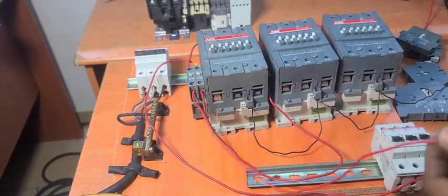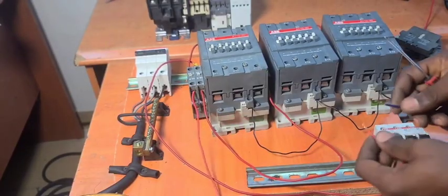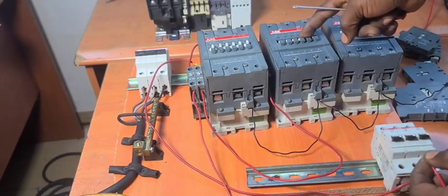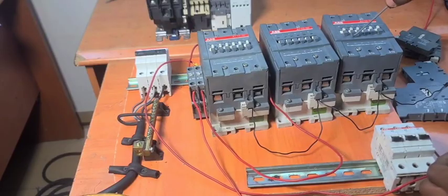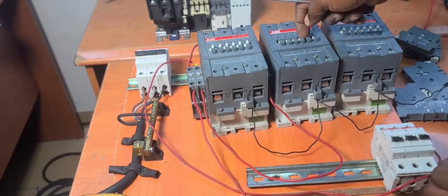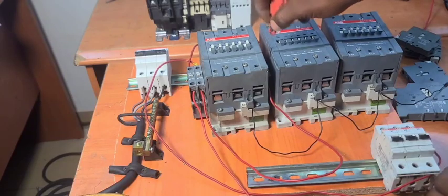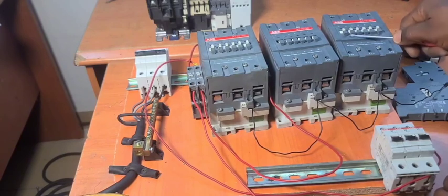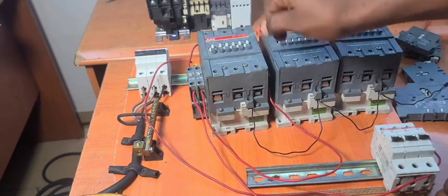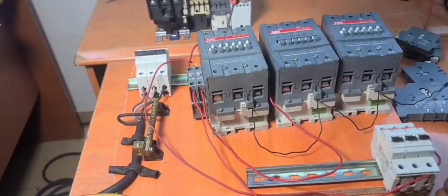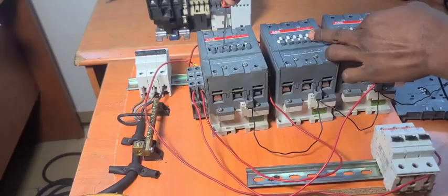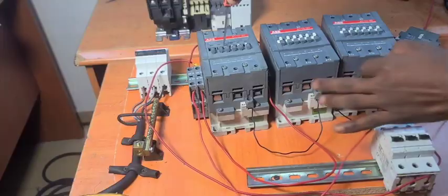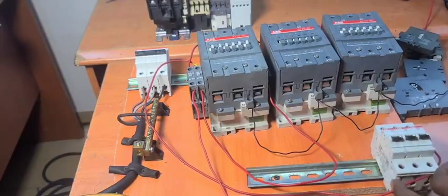So this, if we're going to test it, connect power to it. You see this one has depressed. So this particular one cannot close because this one is depressed. And this normally closed auxiliary that is here is open, meaning there is no way power can go to this one. Even if you start your generator, it cannot close. All right? But if solar comes back up and this one goes down, this one will open, meaning the two sources of power can never collide. They can never connect together. All right? We'll leave it that way.